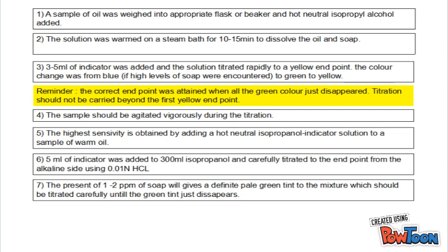Higher sensitivity is obtained by adding hot neutral isopropanol-indicator solution to a sample of warm oil. 5 ml of indicator was added to 300 ml isopropanol and carefully titrated to the endpoint from the alkaline side using 0.01N hydrochloric acid. The presence of 1–2 ppm of soap will give a definite pale green tint to the mixture, which should be titrated carefully until the green tint just disappears.